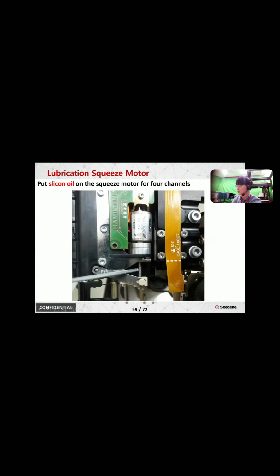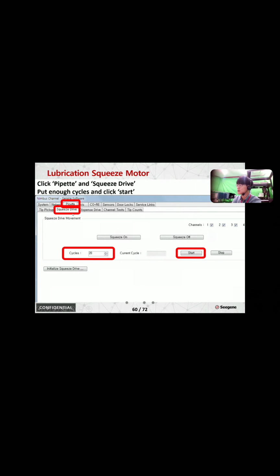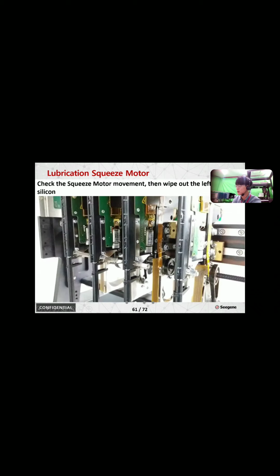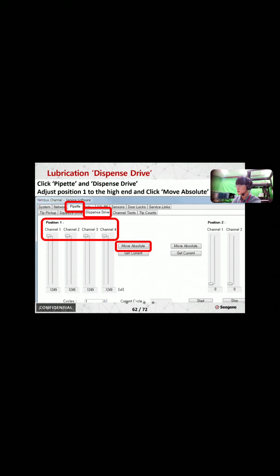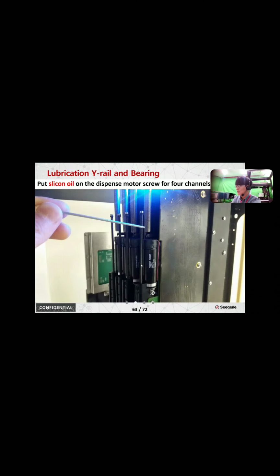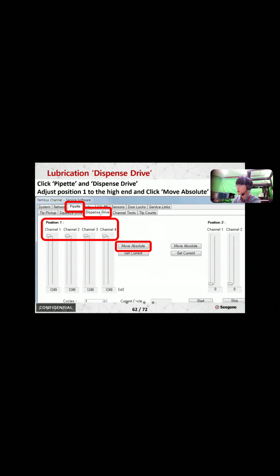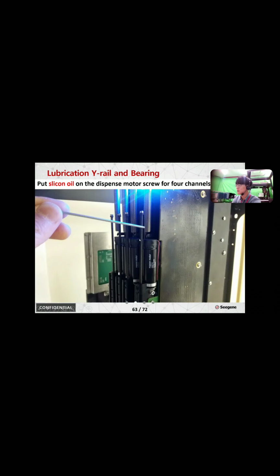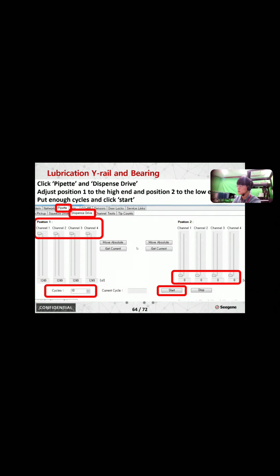Yeah, this is the squeezer motor. The squeezer motor has a small spindle. Put oil on the spindle. Using the service software, pipette squeezer drive, and move it to spread the oil. Dispense motor. The dispense motor does not have a spindle. The pipette head has a spindle, this one. To see the spindle inside, we need to use the software, dispense drive. Move up the spindle, put the oil. Put a little oil and move it to spread it out.